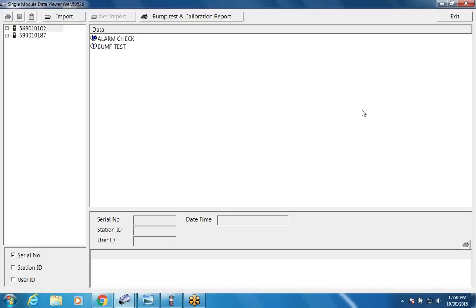The inlet is where you tell it what gas bottles are connected to what inlet port. So I'm telling it now I've got the 5 gas mix connected to gas 1. I don't have anything connected to gas 2 because I don't need anything for the instruments that I have now. And I don't have anything connected to gas 3. But if I had an SO2 sensor, I could put that on gas 2. If I had a HCN sensor, I could put that on gas 3.